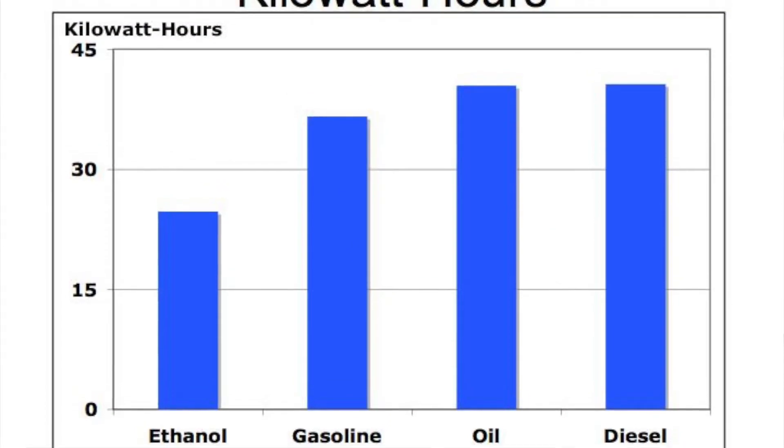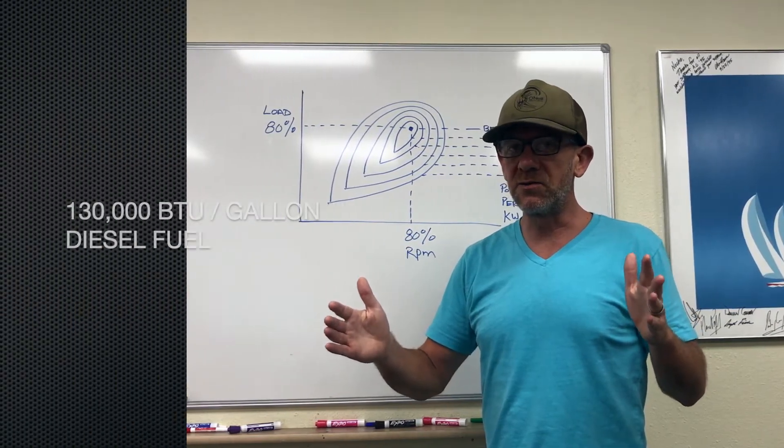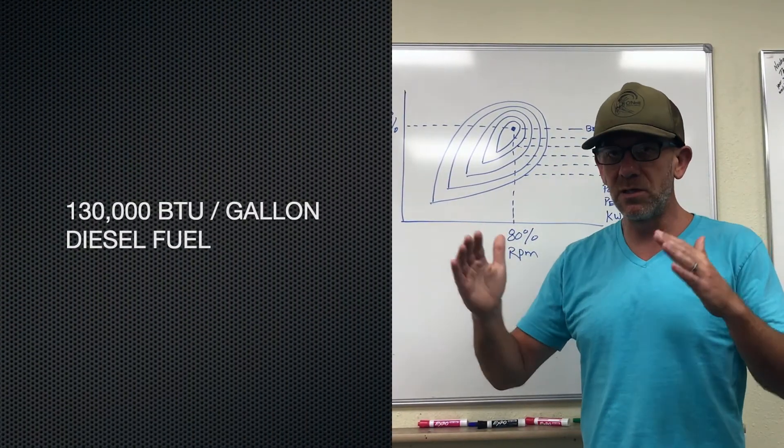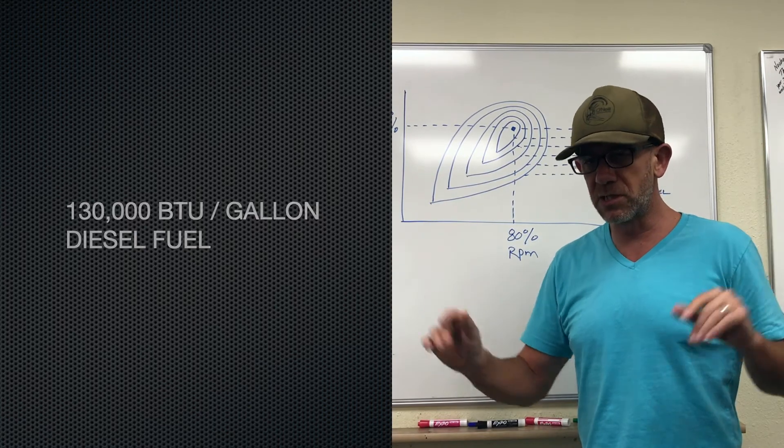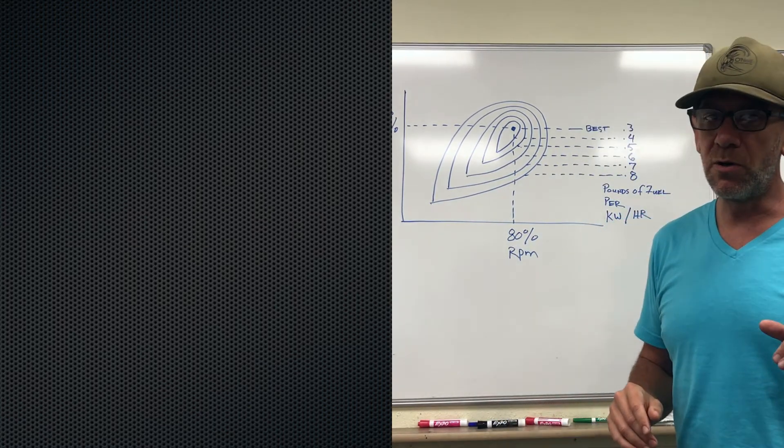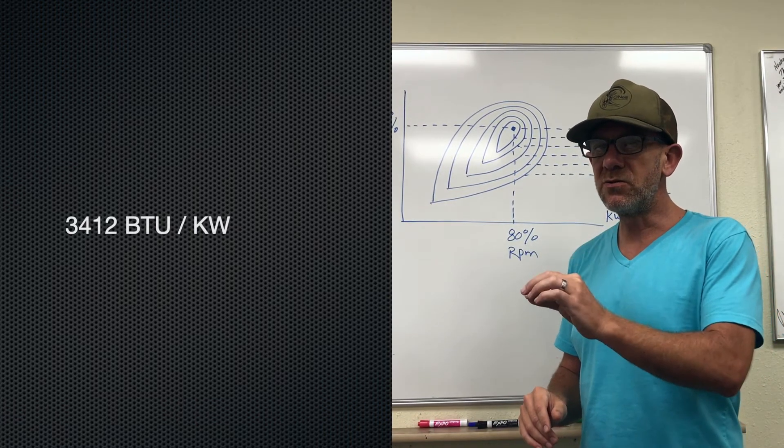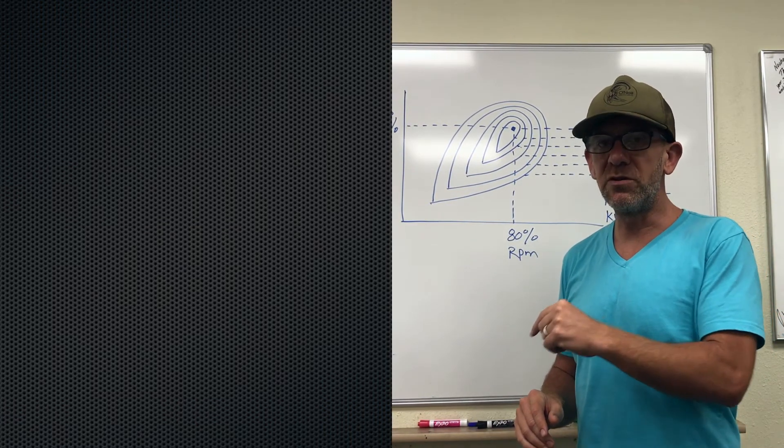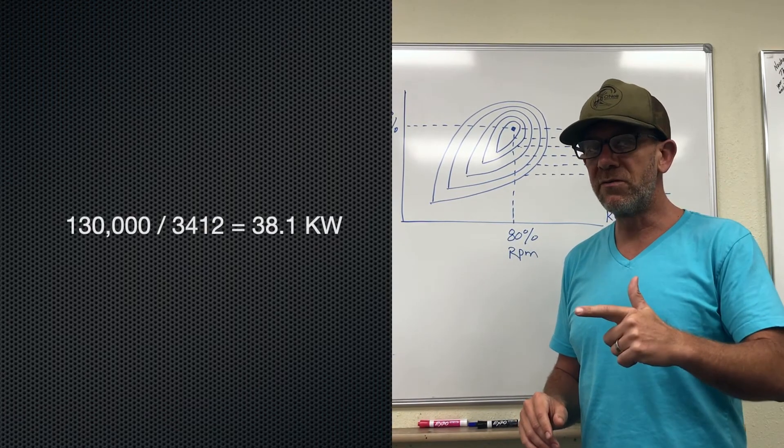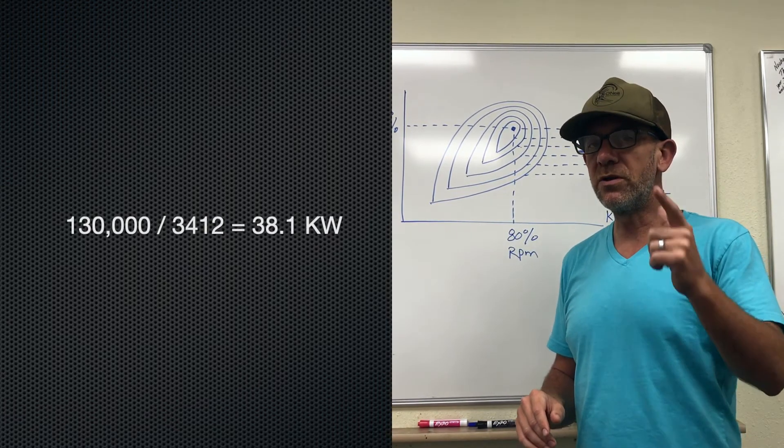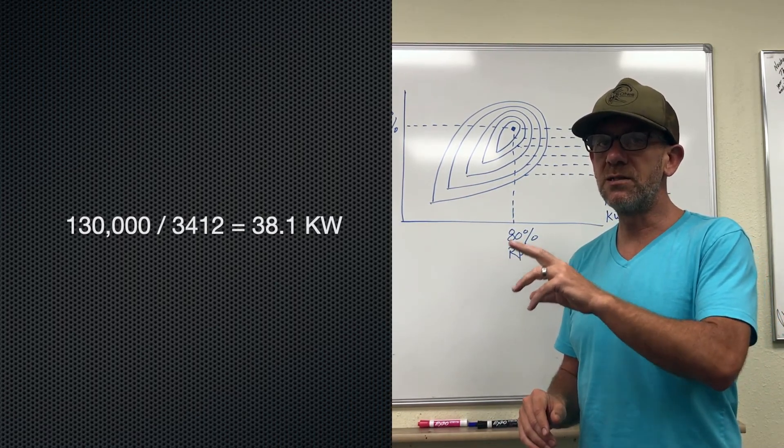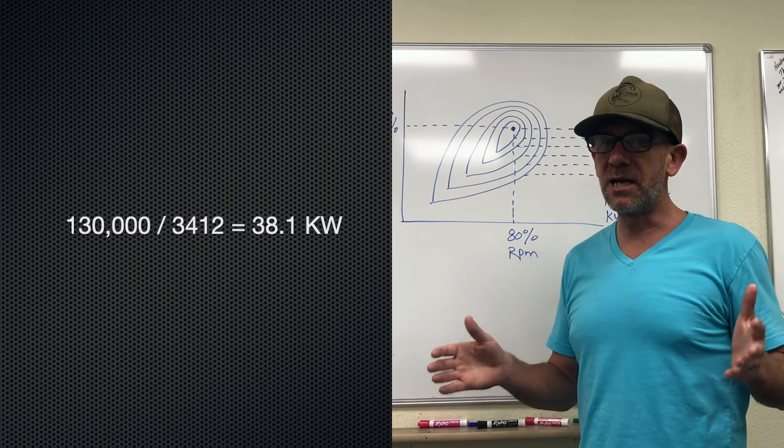What we need to then look at is how much power is available in a gallon of diesel fuel, and we know that's somewhere around 130,000 BTU. It's going to vary a little bit from one diesel fuel to the next, but that's close enough. Now we also know that there's 3,412 BTUs in a kilowatt. So if you divide 130,000 by 3,412, what you end up with is 38.1 potential kilowatts of power in that gallon of diesel fuel.